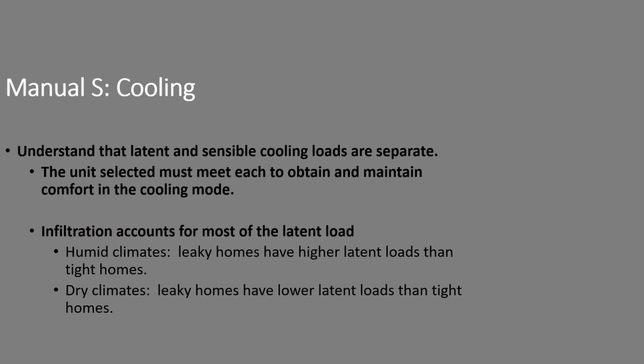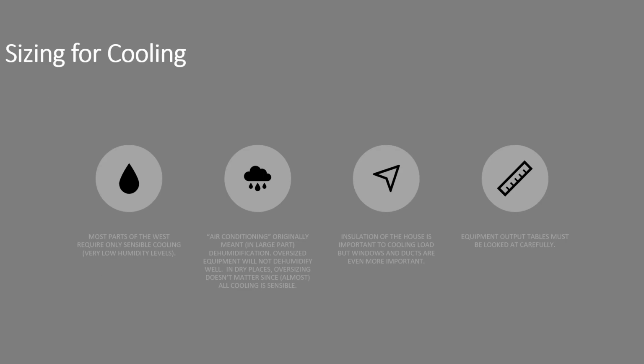Manual S, when it comes to selecting these things, understand that latent and sensible cooling loads are two separate items, and you have to meet each to obtain comfort. In cooling mode, the good news is our latent load is really tiny. Just to show you how this works, infiltration accounts for most of the latent loads. In humid climates, leaky homes let that moisture in. In dry climates, it's so dry outside that the leaky homes tend to have lower latent loads. Sizing for cooling, in most parts of the West, it's easy to handle the dehumidification. Air conditioning originally meant two things: dehumidification and lowering the sensible temperature.